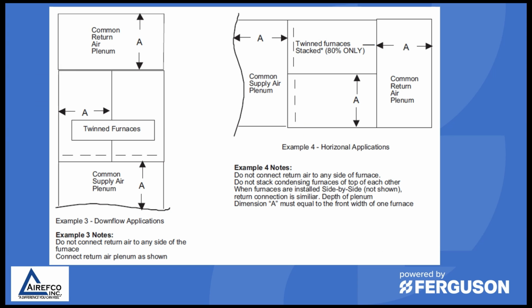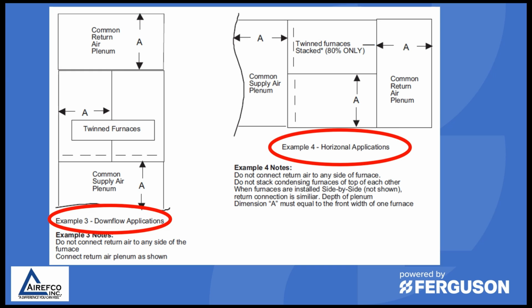Here you see some examples of a downflow application, and again, you have certain measurements that you need to maintain for the furnaces. You also see them for the horizontal applications, and as I stated before, the twin furnaces in some cases can be stacked. And also, any notes that the manufacturer puts on these installation guides, make sure that you follow them to the T when twinning furnaces.